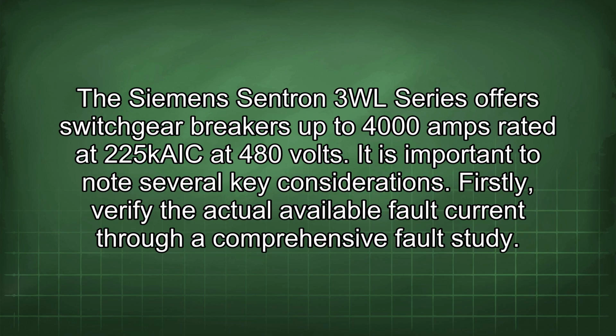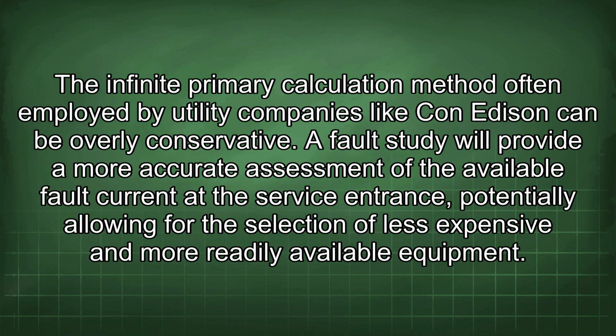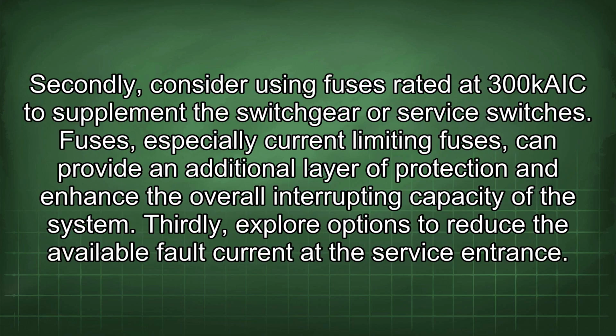It is important to know several key considerations. Firstly, verify the actual available fault current through a comprehensive fault study. The infinite primary calculation method often employed by utility companies like Con Edison can be overly conservative. A fault study will provide a more accurate assessment of the available fault current at the service entrance, potentially allowing for the selection of less expensive and more readily available equipment. Secondly, consider using fuses rated at 300kAIC to supplement the switchgear or service switches. Fuses, especially current-limiting fuses, can provide an additional layer of protection and enhance the overall interrupting capacity of the system.